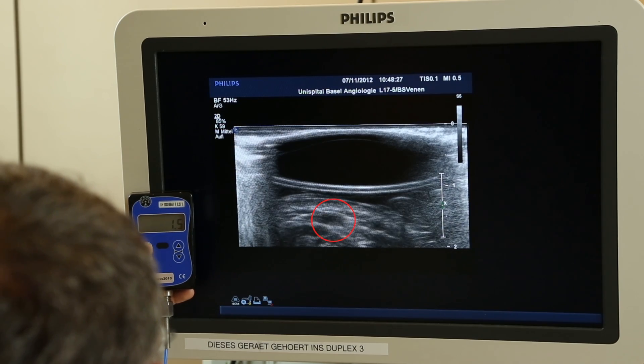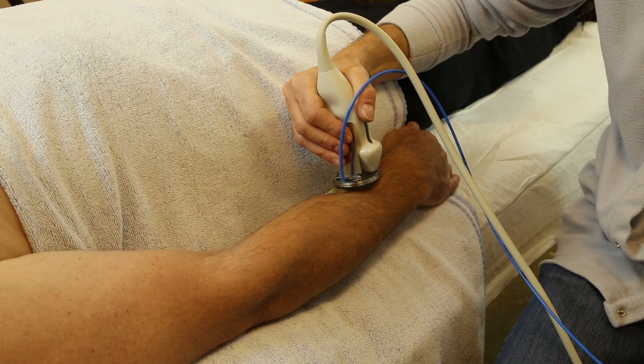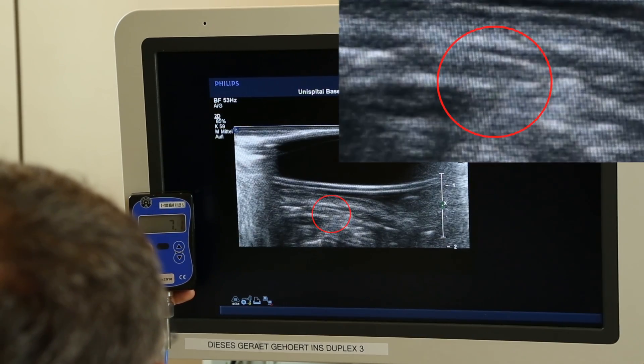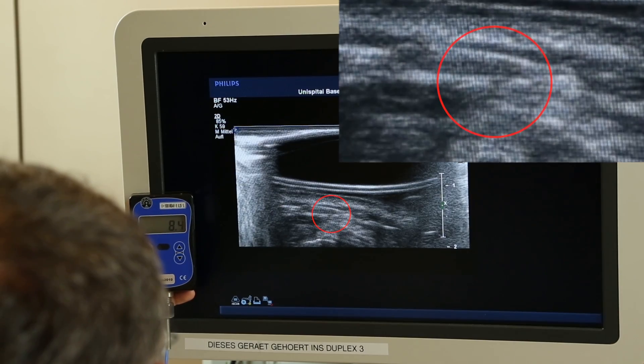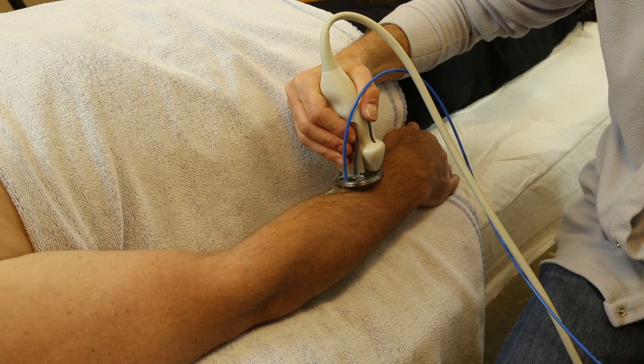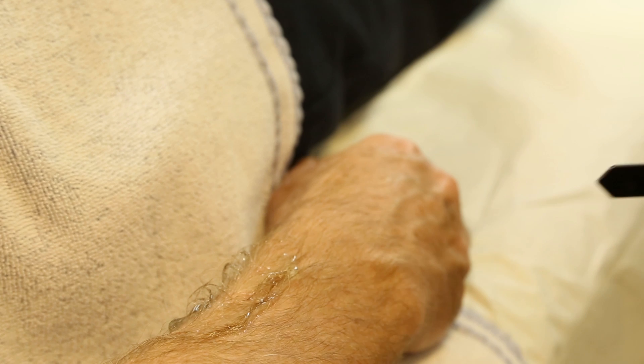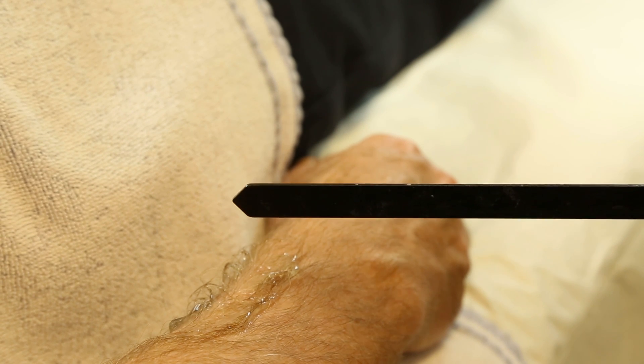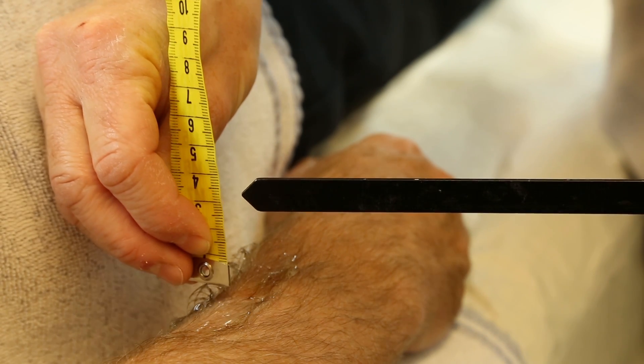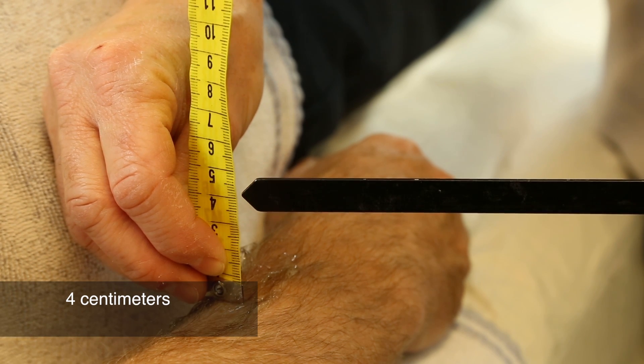Now the vein is compressed slowly several times until the lumen of the vein is occluding. Vein Press measures the intravenous pressure with high precision. In order to calculate the central venous pressure (CVP), the distance to the heart level is measured and subtracted from the intravenous pressure — in our example, 4 cm of water column.